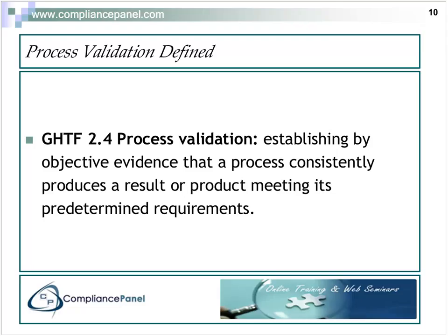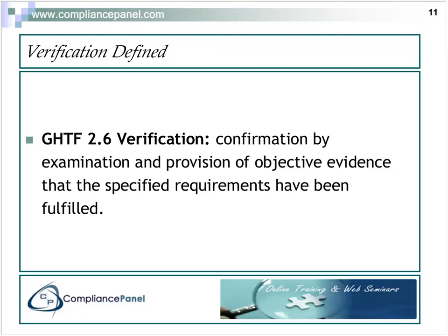So we may, in some cases, rely on a supplier to perform the process validation and provide this objective evidence for us that we must have on hand to demonstrate to the FDA that this has been completed. Now, I talk about the FDA here. Process validation is also a requirement of other regulatory bodies other than the FDA. So I will talk about FDA, but imply that we have to meet the requirements of other regulatory bodies as well.